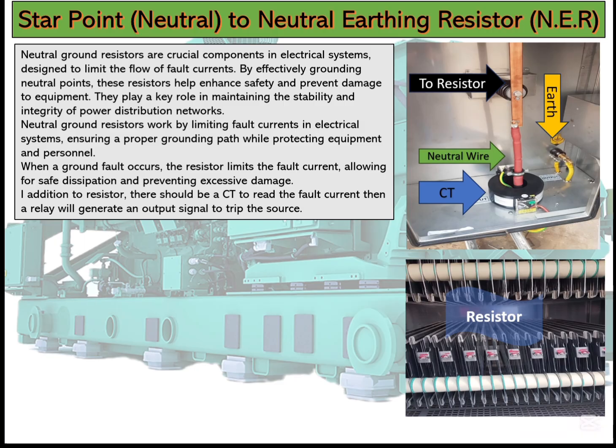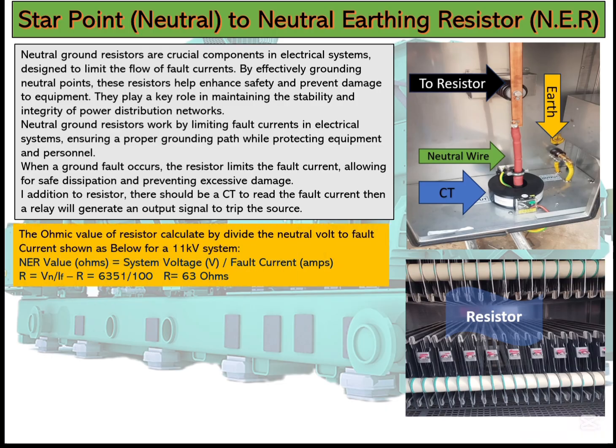When any current passes through this neutral, this CT will read the current and tell the relay. So whenever any current passes, we can set the setting normally. Those settings are 5% or 10% of your rated current. Whenever that current passes, the relay will send a signal to your generator for a shutdown. Because whenever the relay detects any ampere value that meets the set point and threshold, it will shut down your engine. Meanwhile, this resistor will limit the current. It will reduce the short circuit or arc fault current before it travels to the meter, so that our source will remain safe.